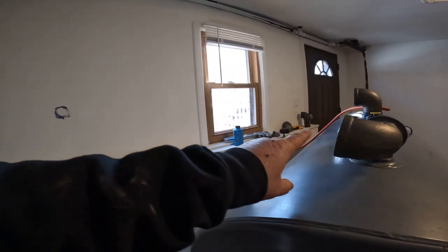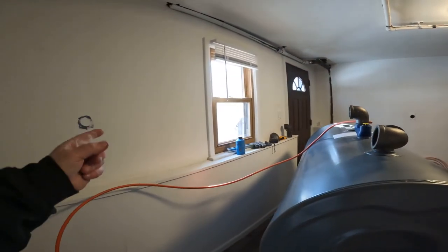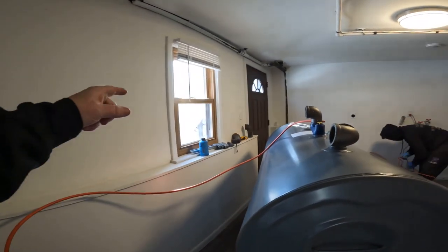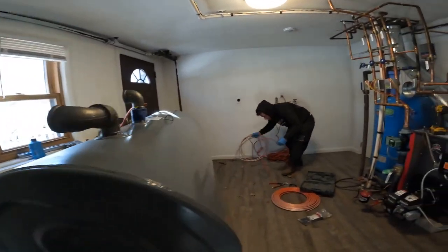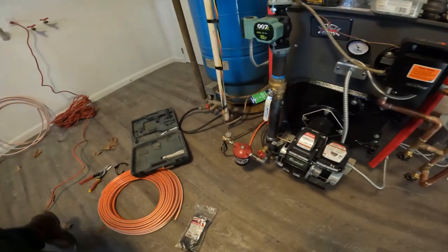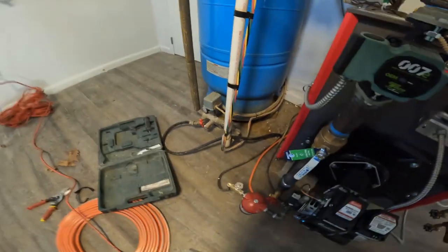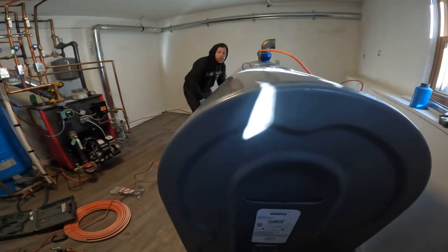You'll need one 40-foot roll of copper. Once we get here, from there to there, it's gonna be a 2-inch black pipe threaded on both sides. The same with that. Once we get over to the burner, we need all the flare fittings to install with that. You don't have the sight gauge or cone.